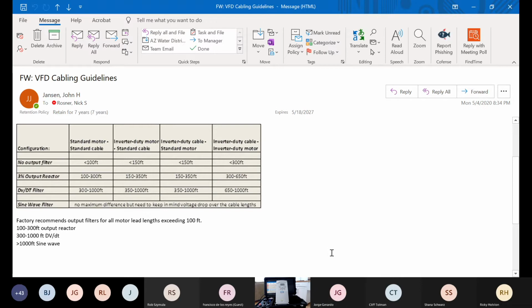So obviously, when you have inverter duty cable, you have more of an allowance to go longer from VFD to motor without having to add reactors, dV/dt filters, or sine wave filters on the output. If you have an inverter duty cable and inverter duty motor, you can go up to 300 feet without having to add an additional component on the output of the drive. So thanks for that. Let me see if there are any other questions.